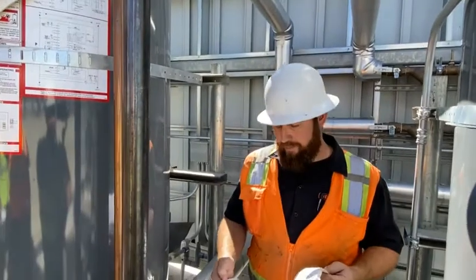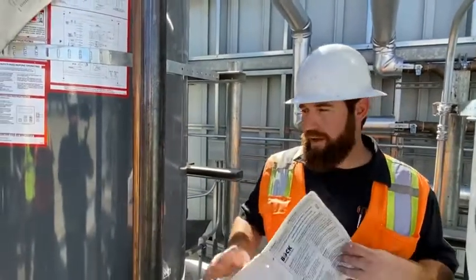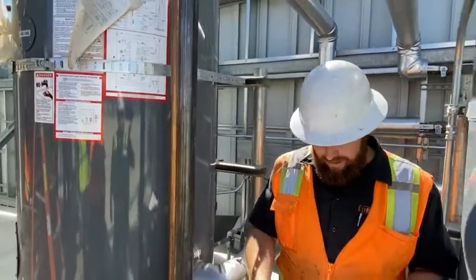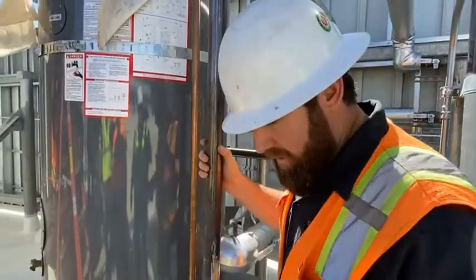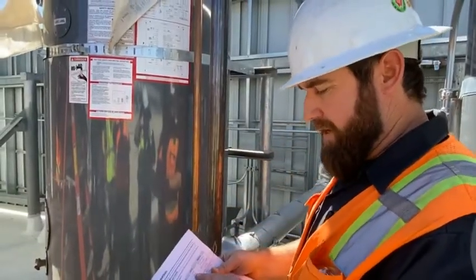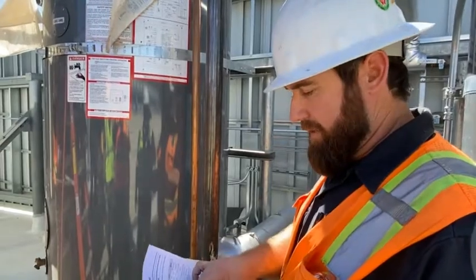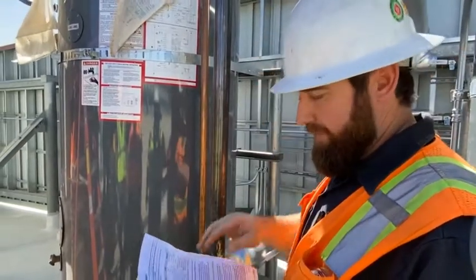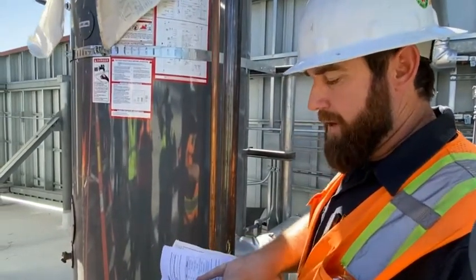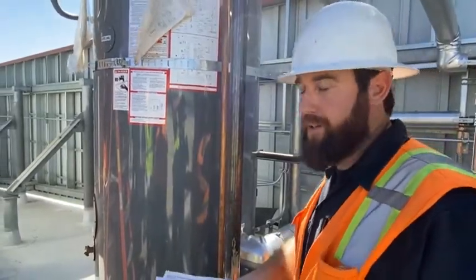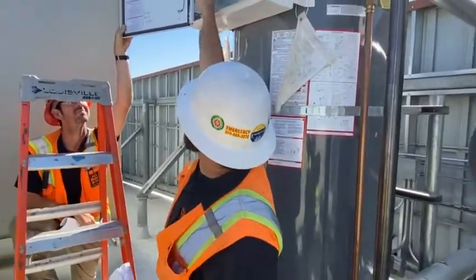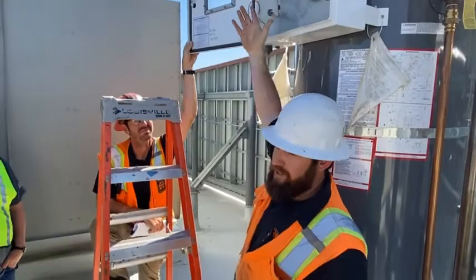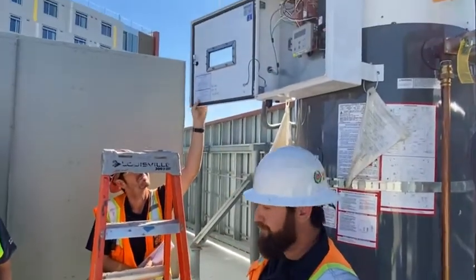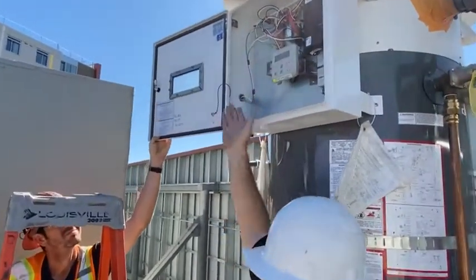As far as maintenance on these goes, it's pretty basic. It says every year check water piping, make sure there's no leaks. Check the relief valve every year. And every 3 months, check the powered anode system, which is this little light right here. Green means good, red is bad. It's really hard to see, but green is actually on right now.